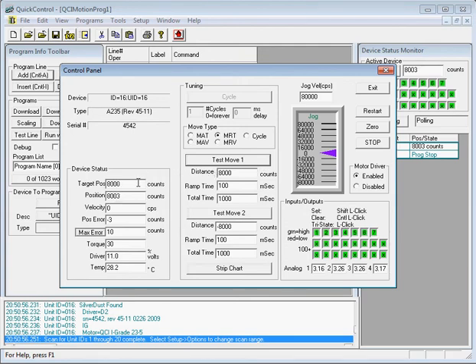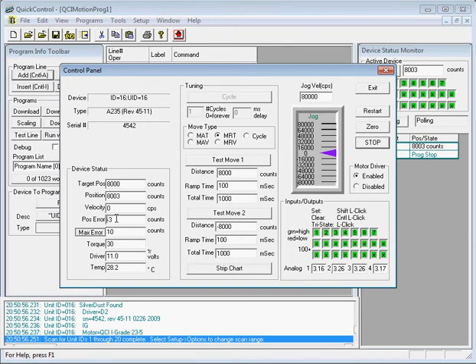As you can see, the target position is 8,000. The actual position is 8,003. There is a position error of 3 counts. Now the position error of 3 counts is due to our anti-hunt feature that prevents the motor from dithering or hunting to its exact position, as long as the position error is small and within error limits.